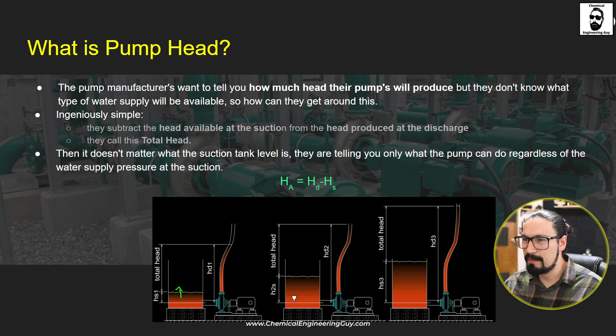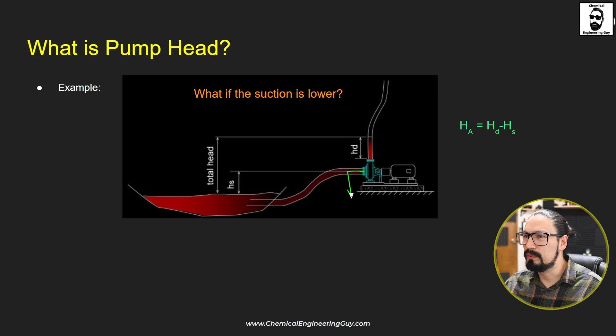All were levels above the suction line, but what will happen if we have a level below the line? This is not great news. The pump will still produce the same total head - that's the key point. So the total head, if this is the same scenario, will be 10.